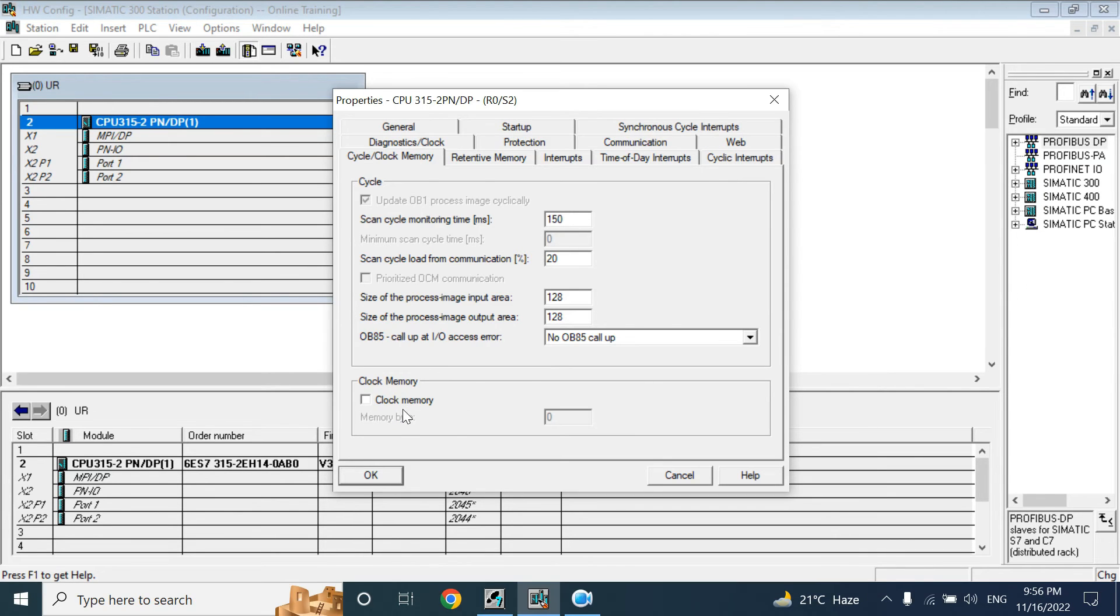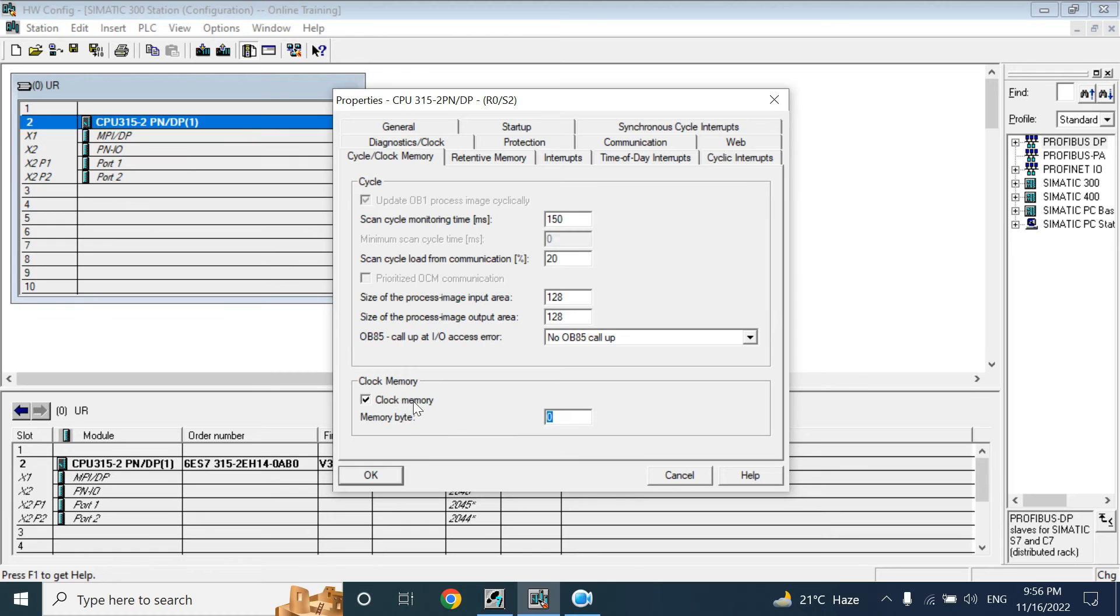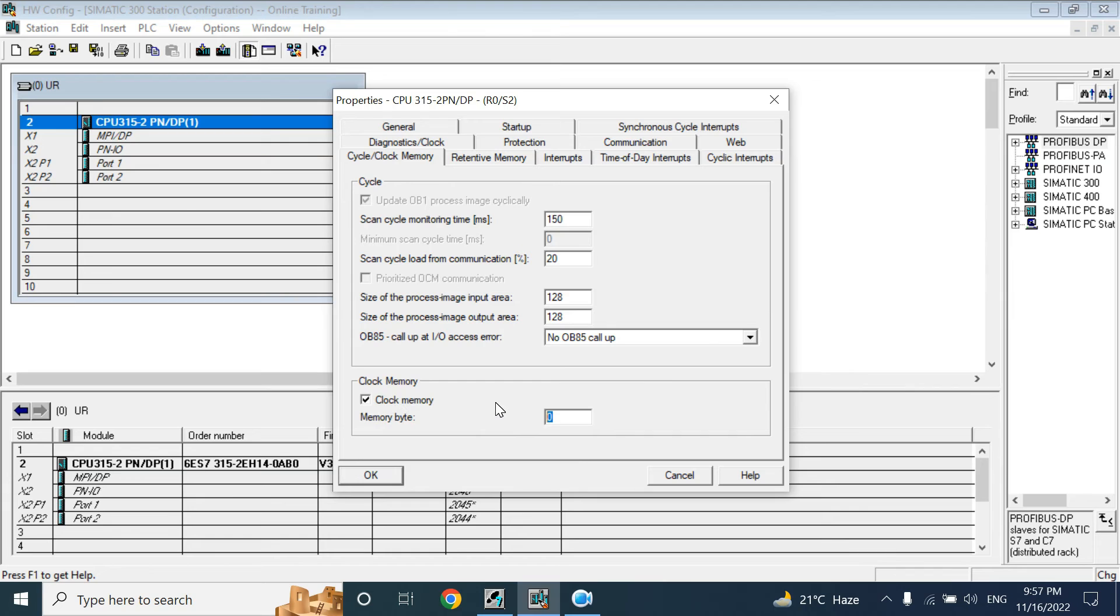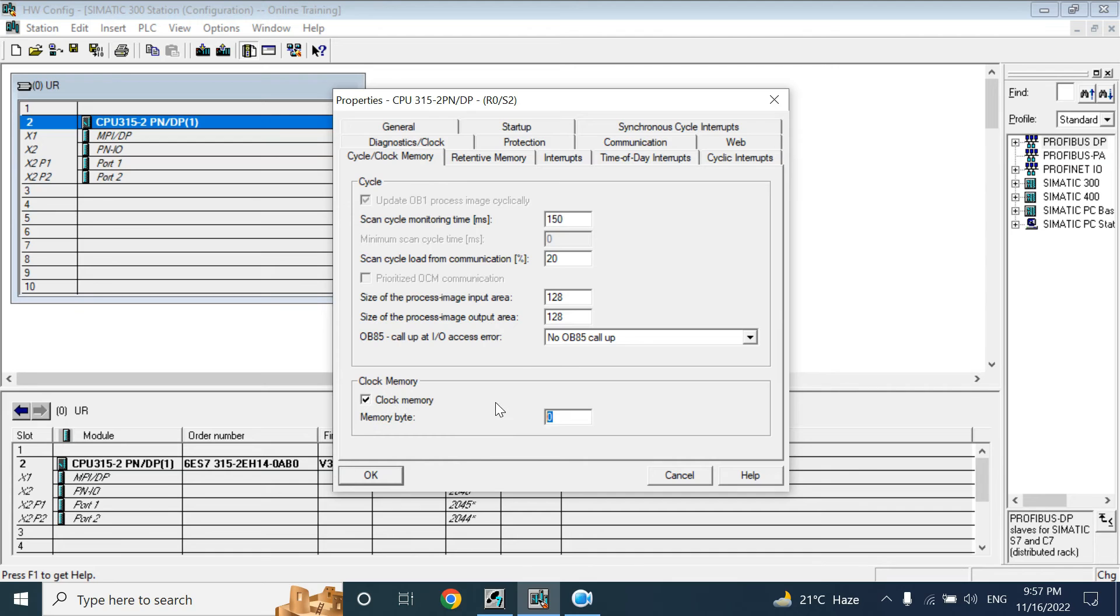Here we can select the clock memory byte. By default it is 0. That clock memory byte is very important. That will give us the pulse, number of pulses, which we can use in our program: 10Hz pulse, 1Hz pulse, 2Hz pulse, 5Hz pulse, like that. We will use that byte or pulse in our program.